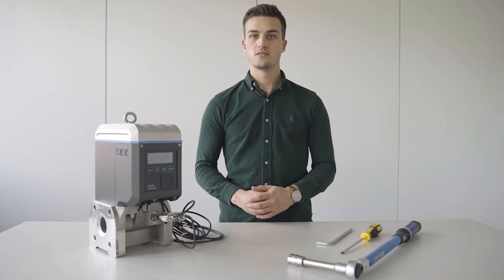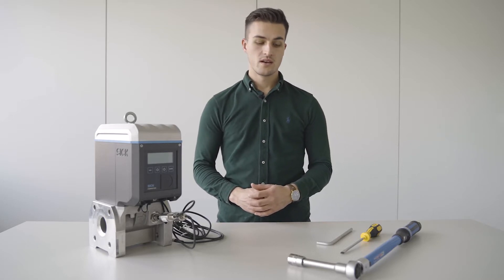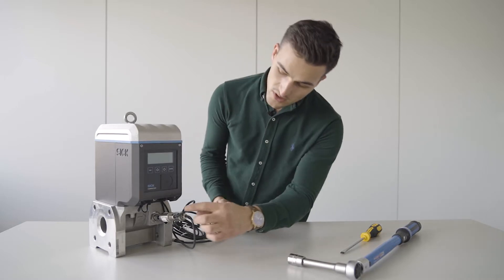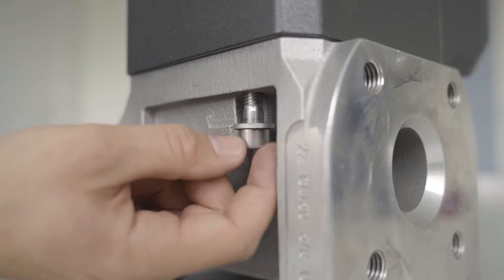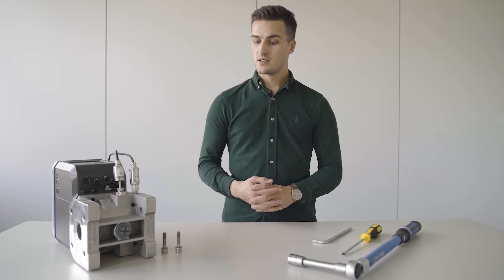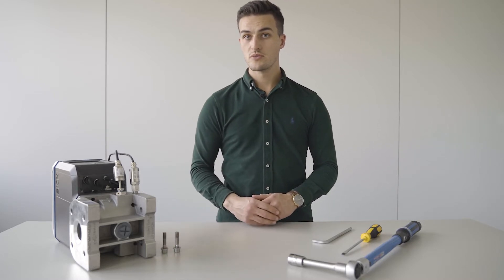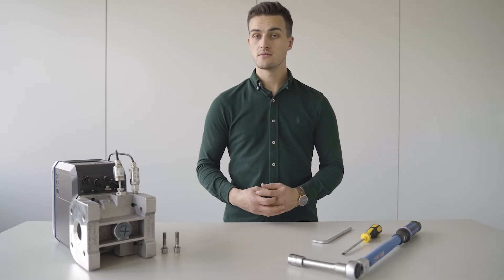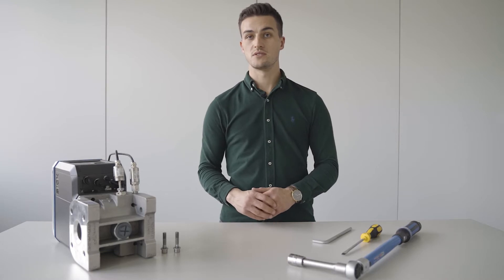Our first step will be to loosen the securing screws of the meter. They are located in the front of the meter right here and on the other side at the back. As you can see for our demonstration purposes, we have laid down our FLOWSIC 500. We have removed the securing bolts from the meter and the next step will be to loosen the securing cap at the very bottom of the meter with a screwdriver.